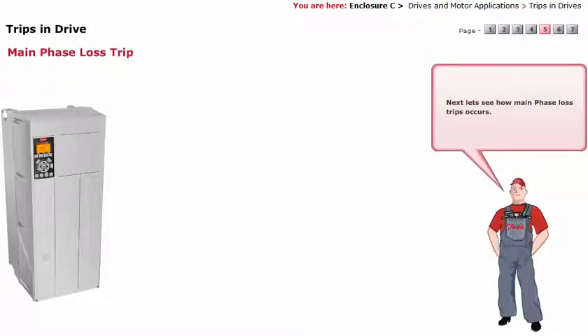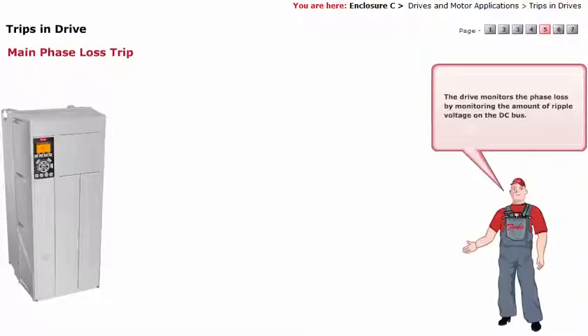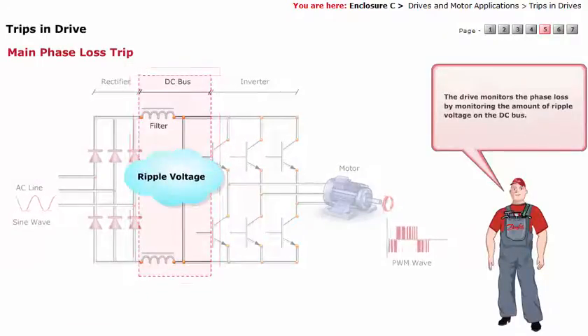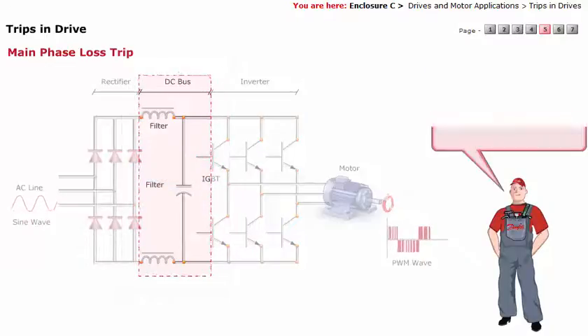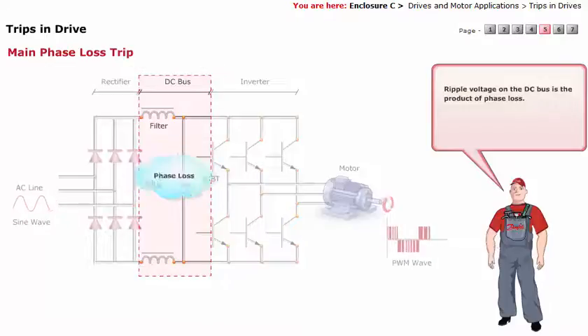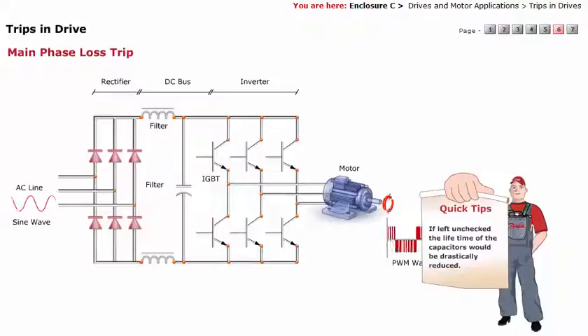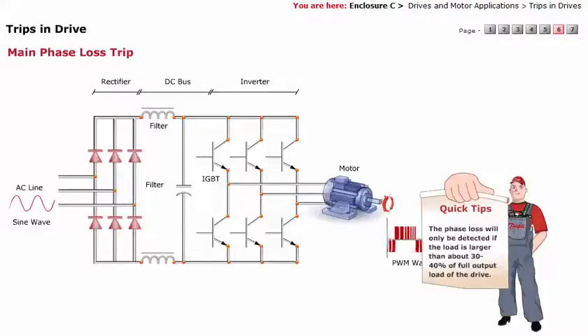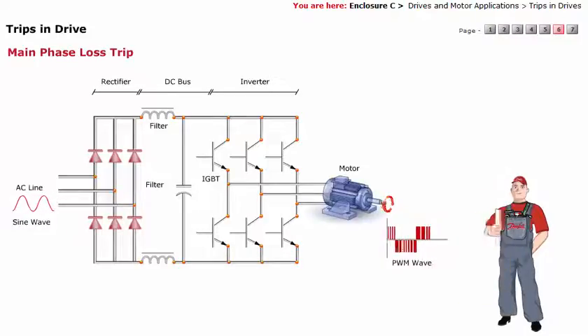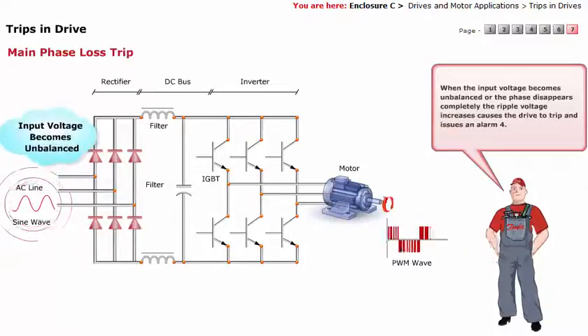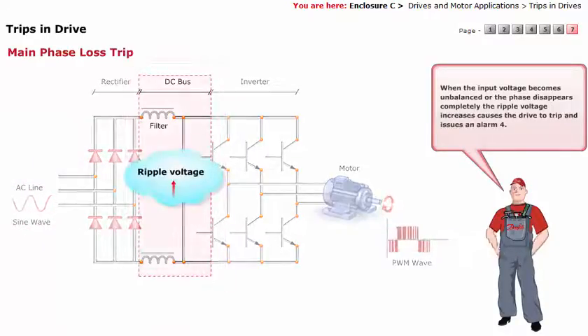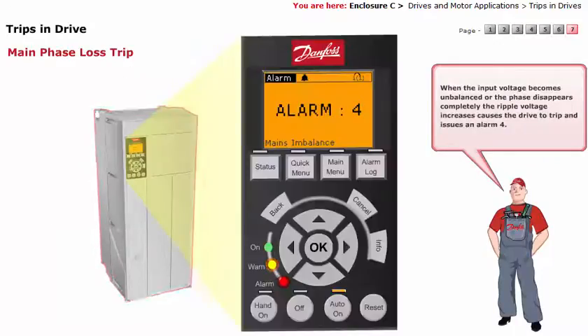Next, let's see how main phase loss trips occur. The drive monitors phase loss by monitoring the amount of ripple voltage on the DC bus. Ripple voltage on the DC bus is the product of phase loss. The ripple voltage causes overheating in the DC bus capacitors and the DC coils. If left unchecked, the lifetime of the capacitors would be drastically reduced. The phase loss will only be detected if the load is larger than about 30 to 40% of full output load of the drive. When the input voltage becomes unbalanced or the phase disappears completely, the ripple voltage increases, causing the drive to trip and issue an alarm.